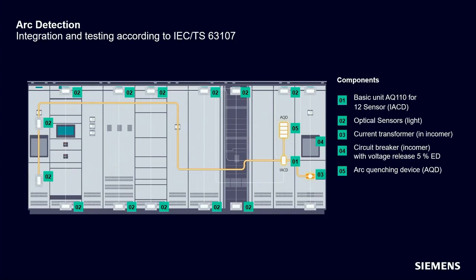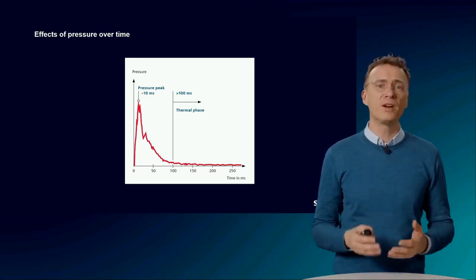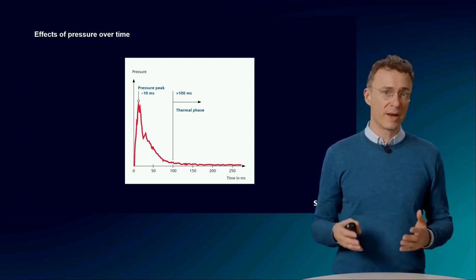All of this happens very fast — within about 15 milliseconds until the circuit breaker has switched off, which means the impact on the system is significantly reduced. In order to ensure protection even in the event of an arc fault occurring on the primary side where the CTs would not measure current flow, a special pressure sensor is available that trips the upstream distribution in medium or low voltage. To reduce the stress even further, this system can also be combined with a quenching device, which reacts so quickly that it can get ahead of the peak of the pressure curve and reduce the mechanical load on the system.